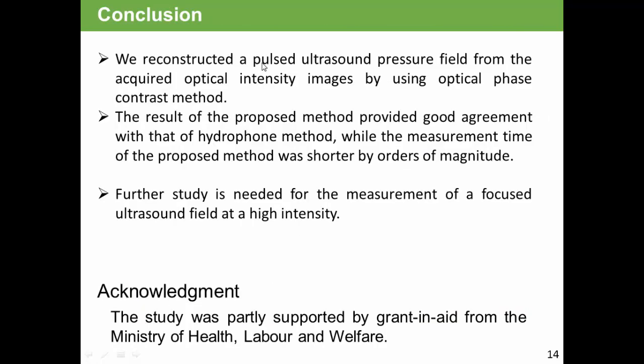In conclusion, we reconstructed a pulsed ultrasound pressure field from the acquired optical intensity images by using optical phase contrast method. The result of the proposed method provides good agreement with that of the hydrophone method, while the measurement time of the proposed method was shorter by orders of magnitude. Further study is needed for the measurement of focused ultrasound field at high intensity. Thank you for your attention.